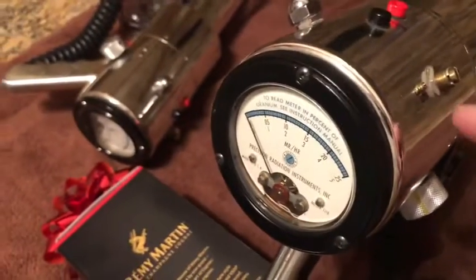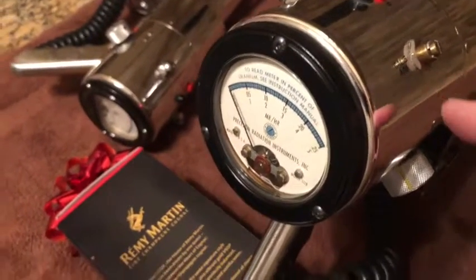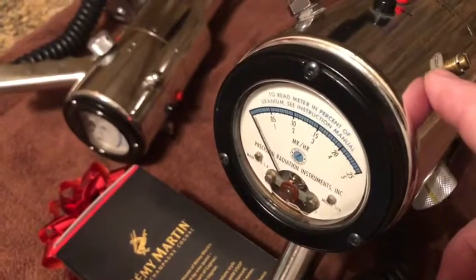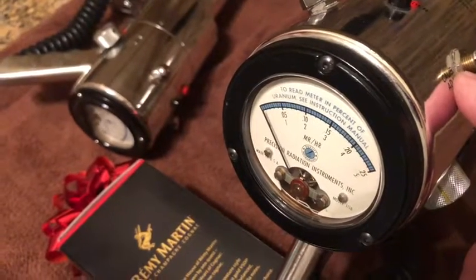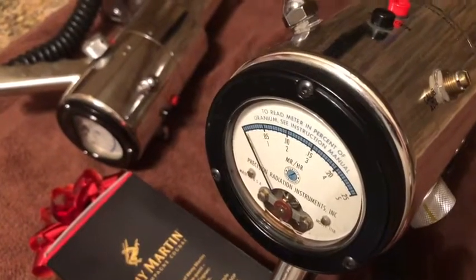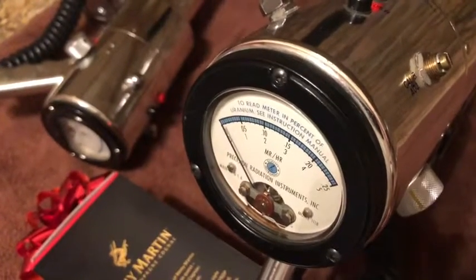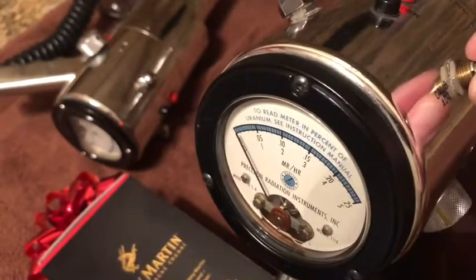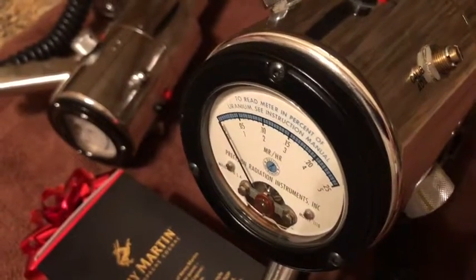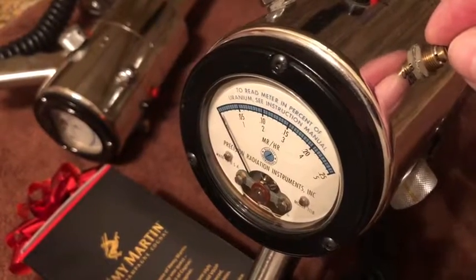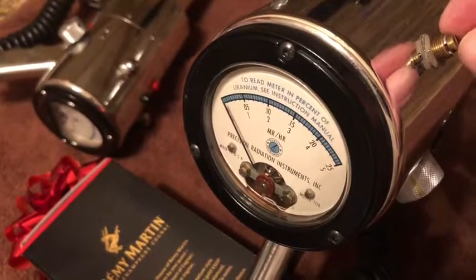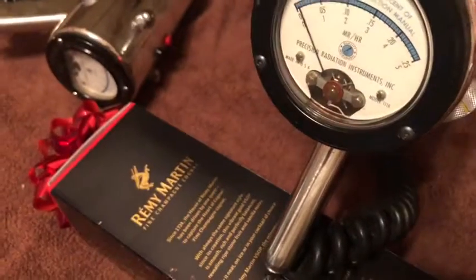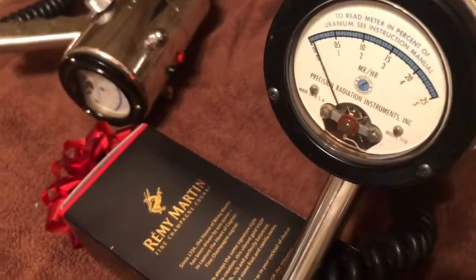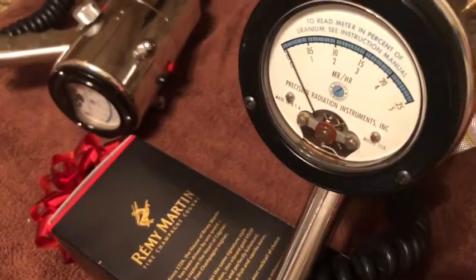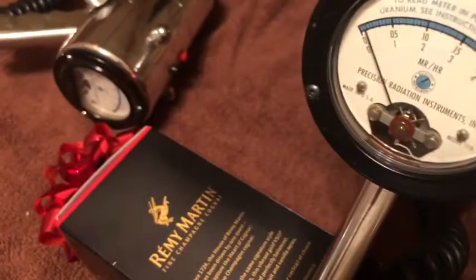One more thing about the calibration adjust. The first 50% or so of the range in the calibration adjust, these things usually have a dead response, and the last portion of the range has a very steep rise. So the very slightest turn with the screwdriver will give you quite a bit of adjustment. You just have to be careful with this. You're not going to break anything. It's just that you'll see it's very sensitive, as they all are.